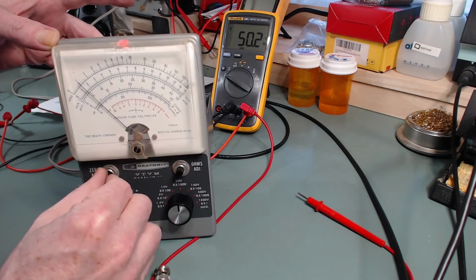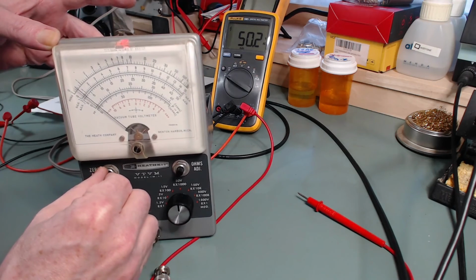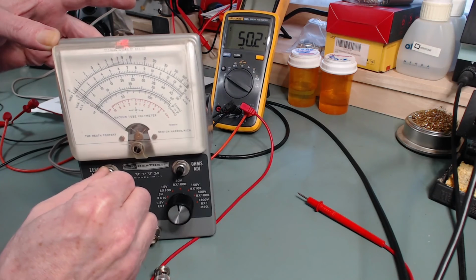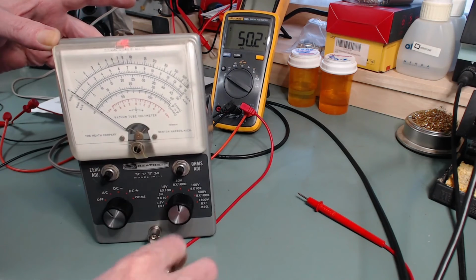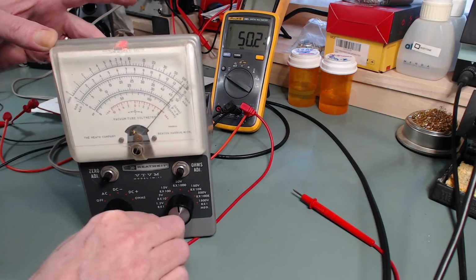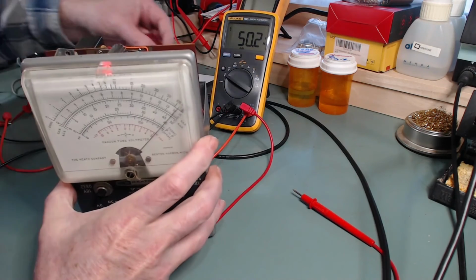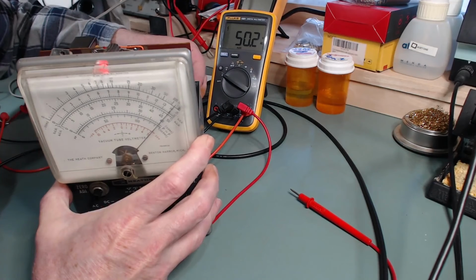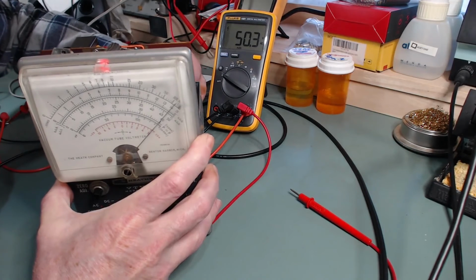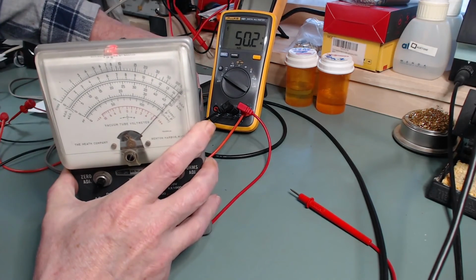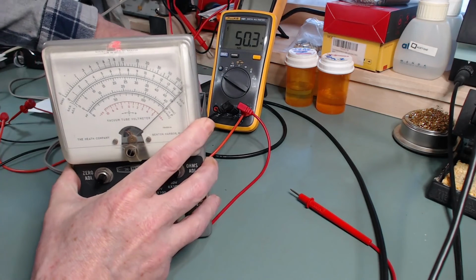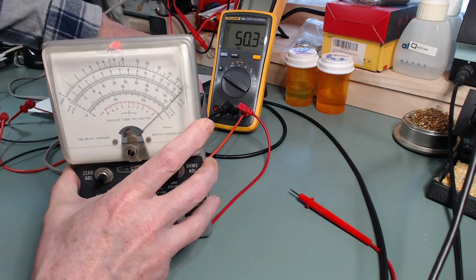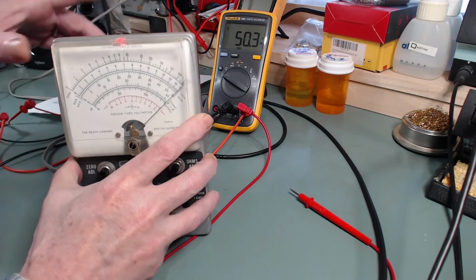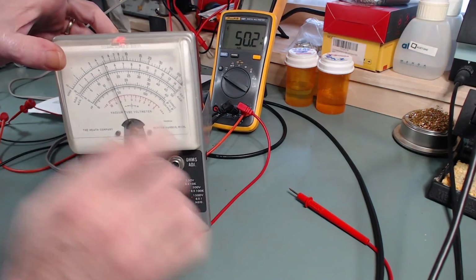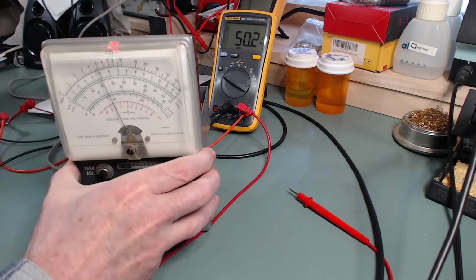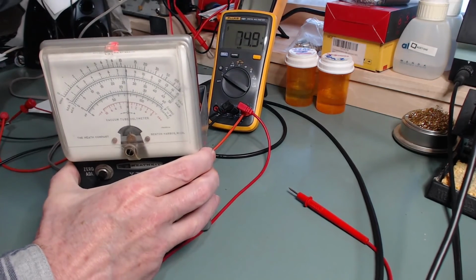Zero out the meter. And recalibrate. Yes, always zero your meter first before you calibrate. Looking straight on. There's 50 volts right there. Come back here. That's reading 50 right on the nose. Turn this back up to 120.